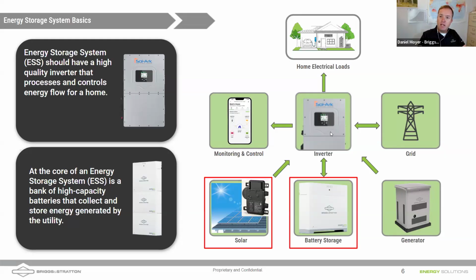Now we can take in microinverters—those look like some enphase IQ7 pluses there—or it could easily be a string inverter, and we can take that AC and feed it into the inverter. Then we take AC down to the inverter, which turns it into DC to charge the batteries, and then we can take that DC out and feed it up to the loads as well.